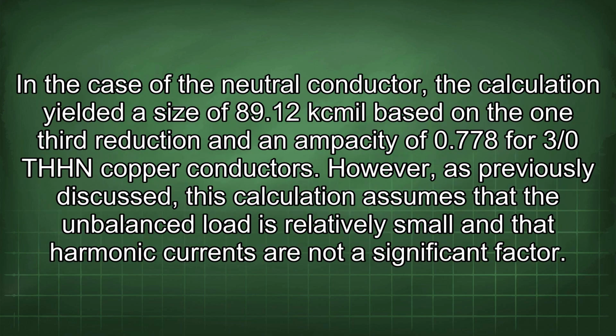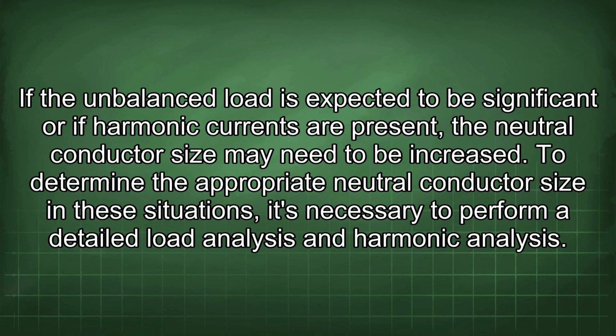In the case of the neutral conductor, the calculation yielded a size of 89.12 kcmil based on the 1/3 reduction and an ampacity of 0.778 for 3/0 THHN copper conductors. However, as previously discussed, this calculation assumes that the unbalanced load is relatively small and that harmonic currents are not a significant factor. If the unbalanced load is expected to be significant or if harmonic currents are present, the neutral conductor size may need to be increased.